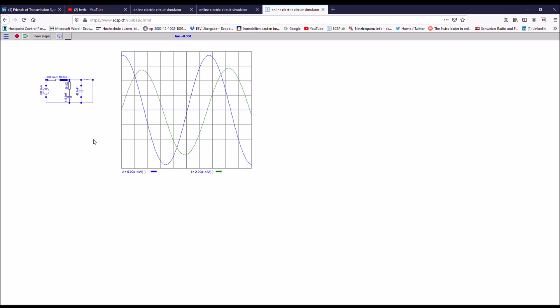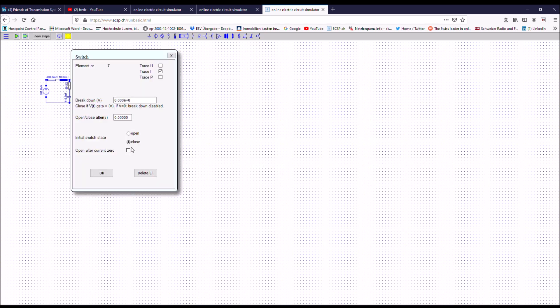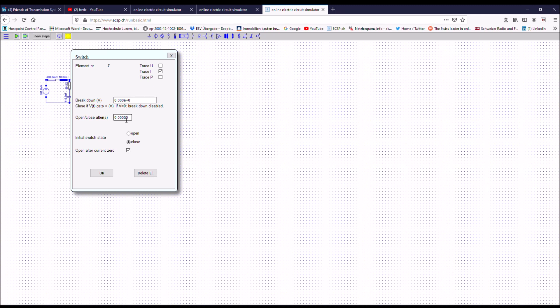Let's now set the timing of the breaker so that it can interrupt the current after the first full cycle here. So that means I would ask the breaker to separate the contacts around about here after 15 milliseconds. First of all, we have to make sure that the breaker opens only after current zero. So let's put this one on yes and then ask the breaker to open after 15 millisecond contact separation.